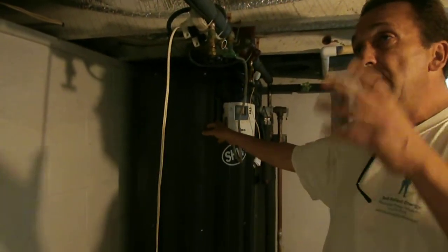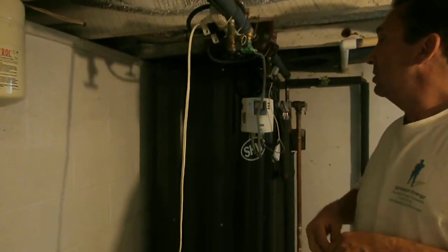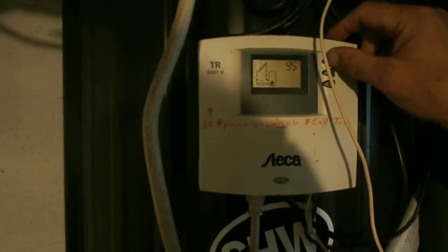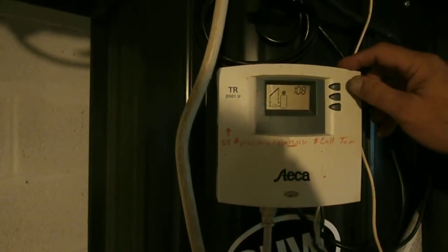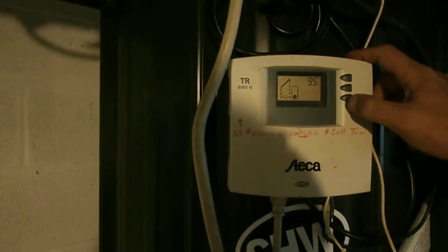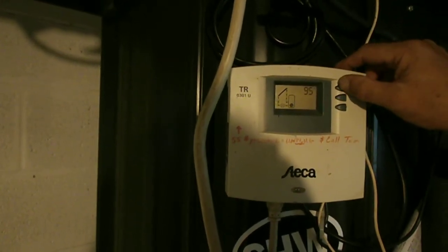We're bringing the hotter water from outside to support the storage tank that's on the inside. Right now the pumps are not circulating, but in our digital readout we have 95 degrees temperature in the tank and 108 degrees outside. We had no sun today, but I am measuring 108 degrees in the top panels outside. The reason the pumps are not circulating is there's not a 20-degree temperature difference between the two. When that panel reaches 20 degrees higher than 95 degrees, then the circulating pump will turn on.